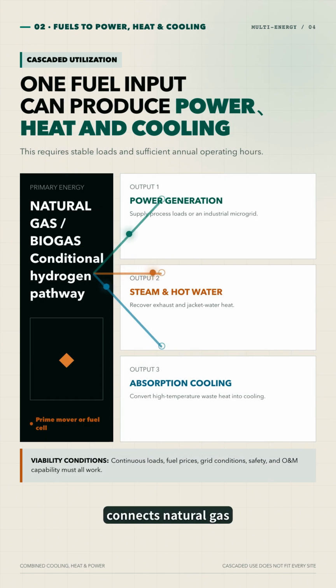The second type connects natural gas or other fuels with electricity, heat, and cooling. Gas turbines, reciprocating engines, or fuel cells can generate electricity. Their high-temperature exhaust heat can then produce steam, hot water, or process heat. If that heat also drives an absorption chiller, the result is combined cooling, heat, and power. This works best where electrical, heating, and cooling loads are stable and annual utilization is high. Biomass, biogas, and selected hydrogen pathways can also enter this system. But fuel availability, continuity, cost, safety, and technology maturity must be verified separately. A concept diagram is not enough.